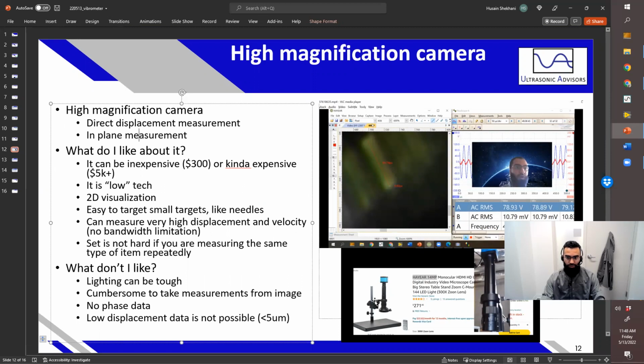The system needed is usually a machine vision or digital camera with a high magnification lens. The lens is called an industrial microscope. That's usually the terminology that's used, because an industrial microscope is not a traditional microscope where you're getting very close to a slide. You actually want some standoff distance so you don't knock your transducer into your lens when you're trying to maneuver it around.